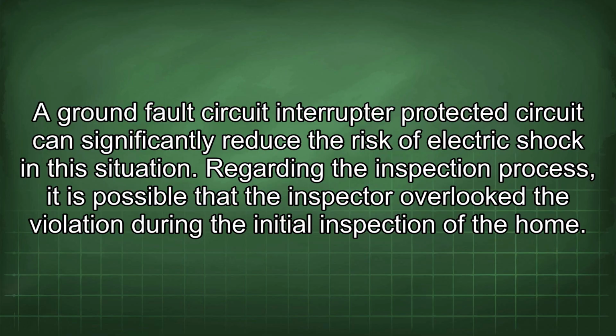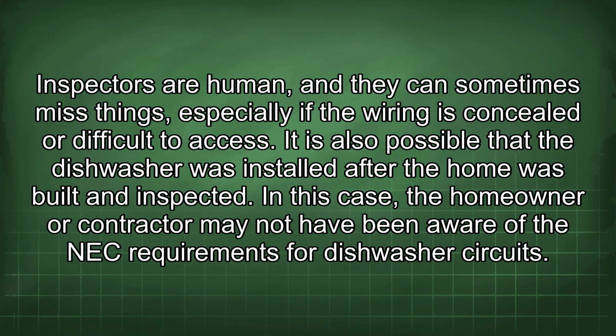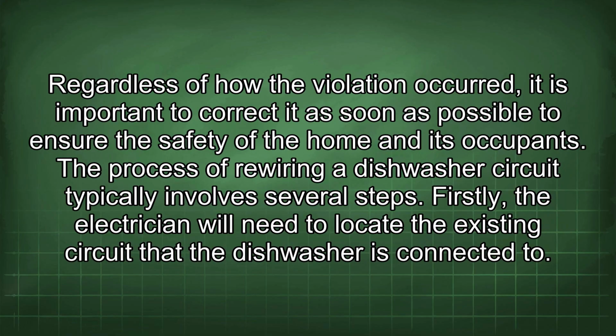Regarding the inspection process, it is possible that the inspector overlooked the violation during the initial inspection of the home. Inspectors are human, and they can sometimes miss things, especially if the wiring is concealed or difficult to access. It is also possible that the dishwasher was installed after the home was built and inspected. In this case, the homeowner or contractor may not have been aware of the NEC requirements for dishwasher circuits. Regardless of how the violation occurred, it is important to correct it as soon as possible to ensure the safety of the home and its occupants.